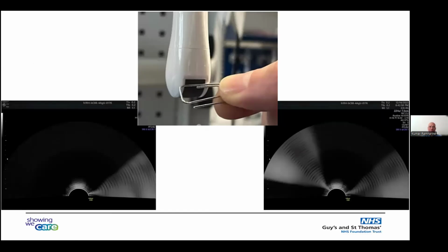You can also make use of reverberation artifacts for testing scanners. When we go to the hospitals and test scanners, we might use a paperclip, as shown here, to look at the reverberation pattern. The paperclip is positioned on the probe. You should only have one reflection, like on the left side, where you have the reverberation pattern. On the right, you have two reflective patterns, and this was a fault in the scanner because of the way they were incorrectly wiring the transducer. It was producing double images, and this was detected as a fault during manufacturing of these probes.